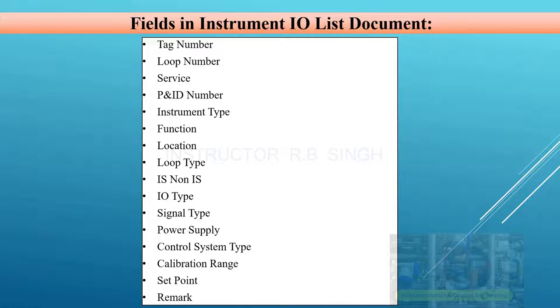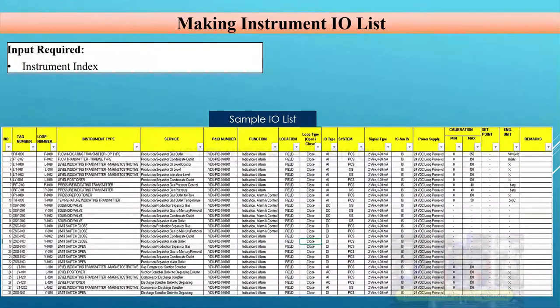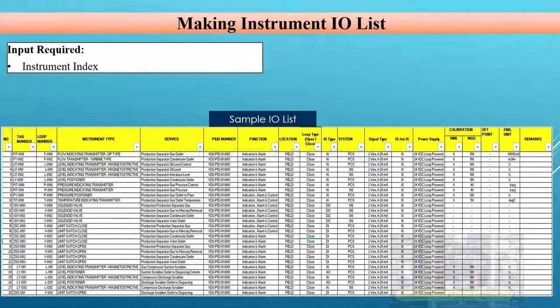Apart from these fields, you can add others per client recommendations or specific data requirements, but these are the most important fields. The input for the IO List is the instrument index. While you can also prepare it based on the P&ID, that takes more time. Since all the activity has already been done in the instrument index, you simply apply filters on the IO type, extract those results to another Excel sheet, fill in additional information, and your IO List will be ready.